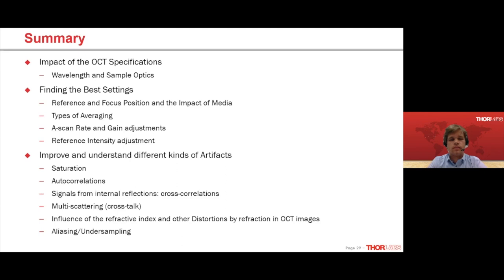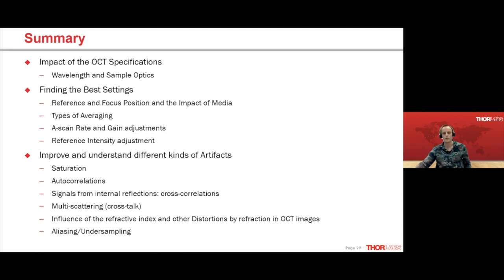Next question from Chris: how is gain adjusted — electronic gain, reference arm power, or something else? We have an electronic gain adjustment. In swept-source OCT, after getting the balanced detection signal, we have several amplification levels that can be adjusted in our software — it's simply an amplification of the electronic signals.